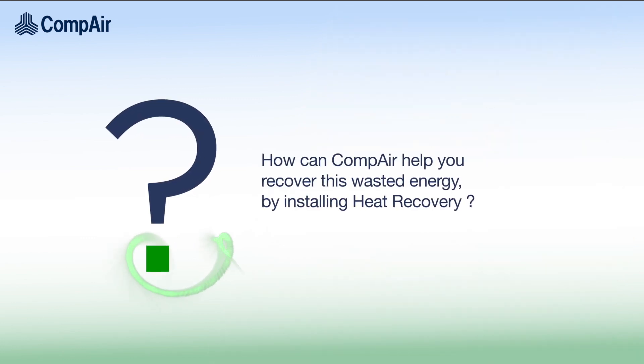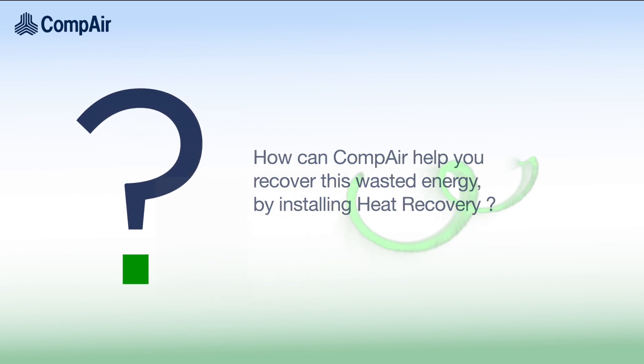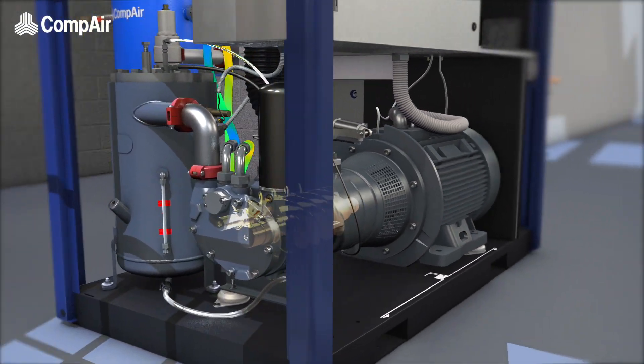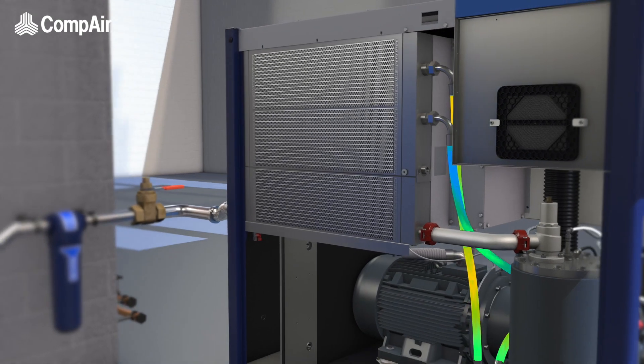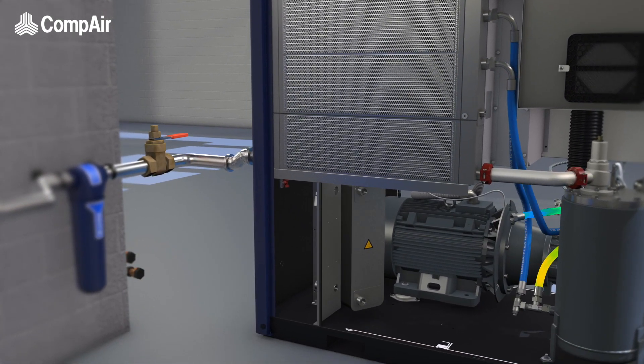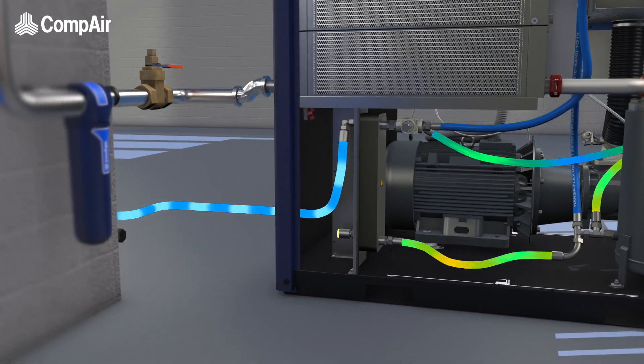So how can CompAir help you recover this wasted energy by installing heat recovery? Heat which is created during compression is absorbed by the cooling oil. This typically would be cooled by an oil cooler. By installing heat recovery, this hot oil would instead pass through a plate heat exchanger where the heat is transferred to an incoming water supply.